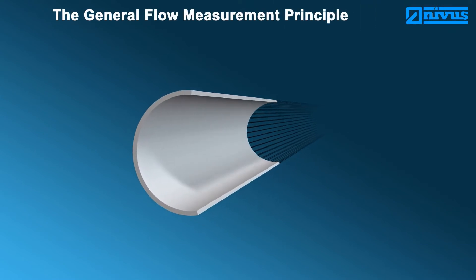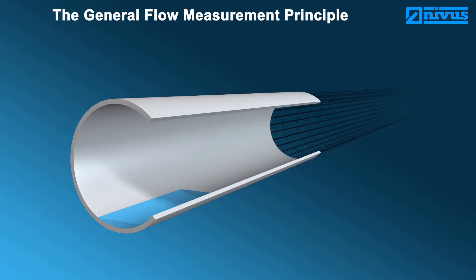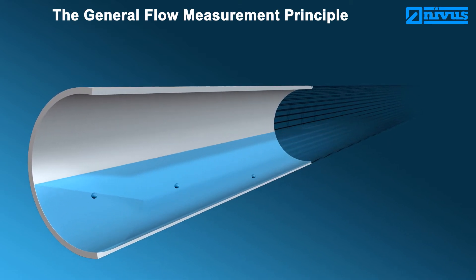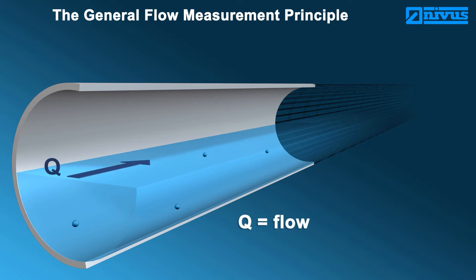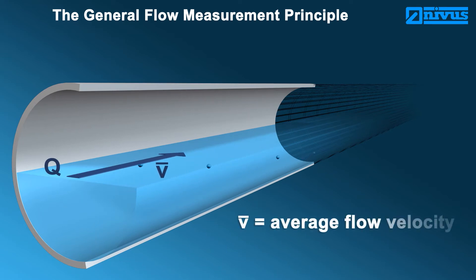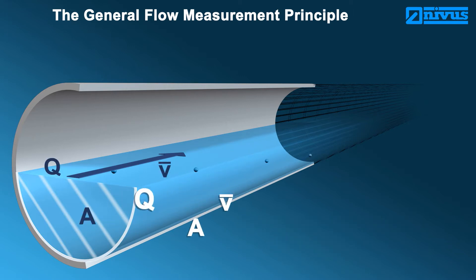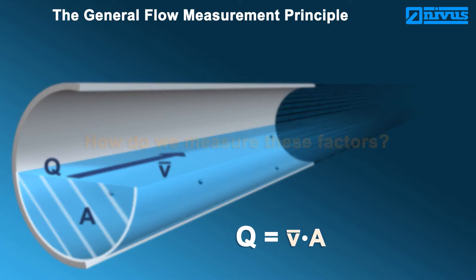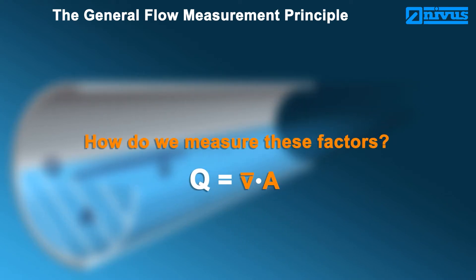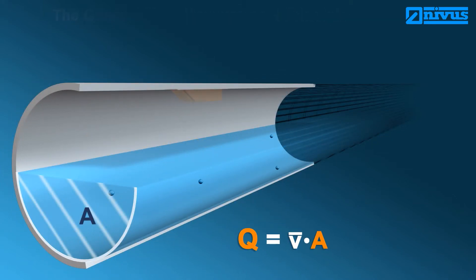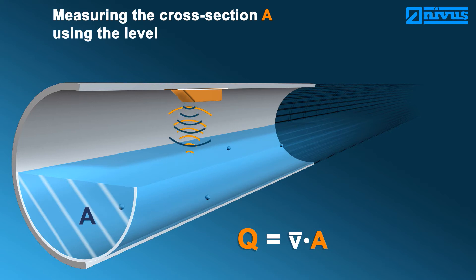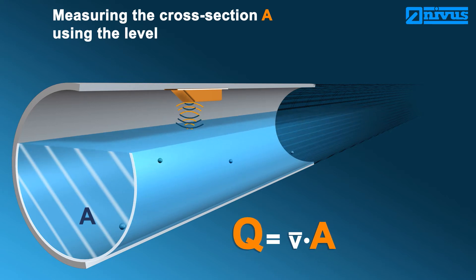The flow measurement principle. Flow cannot be measured directly. There are various factors required to detect the flow Q, such as the average flow velocity and the flow cross-section. From this, the general formula is obtained: Q equals V average times A. The flow cross-section A is determined by continuously measuring the level in consideration of the channel shape. If the level changes, the flow cross-section will change accordingly, and hence flow will change as well.